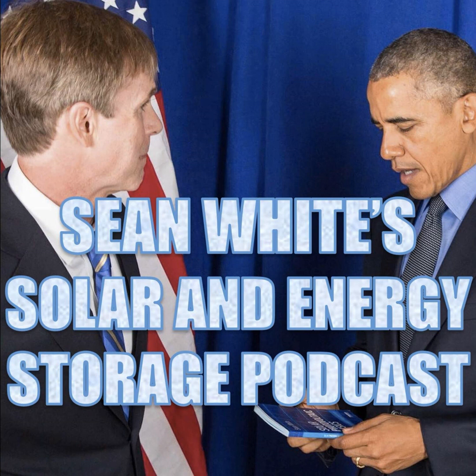One of the things that we like to do is to criticize Article 480 because we're Article 706 people. Storage batteries and battery management equipment shall be listed. So that's a good idea. Listing things. And there's UL 1973, that's the UL listing that's a lot of times used for our energy storage systems. But then this requirement shall not apply to lead acid batteries. So you could almost say here that you could go make some lead acid batteries in your basement. Doesn't that sound exciting? I love working with lead.